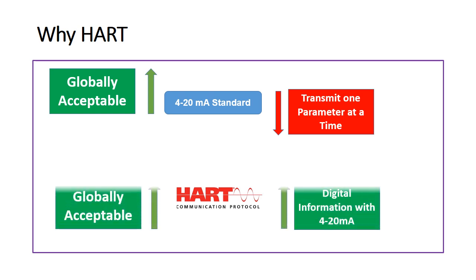Why use HART? As we are all aware, the 4 to 20 milliampere standard is worldwide accepted for analog signals, but there is a major drawback: the 4 to 20 milliampere standard can transmit only one parameter at a time on analog wiring. HART is the answer to this drawback, as it can transmit analog signal as well as digital information at the same time.